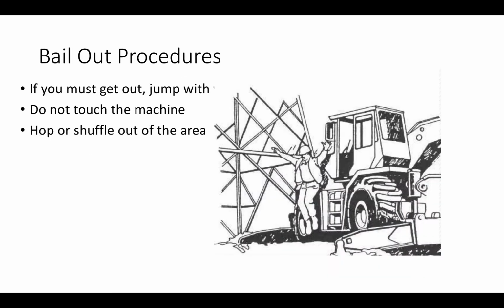If you have to jump out or bail out of a machine that has been connected to a line, jump. Do not touch the machine as you jump. Hop or shuffle out of the area. In other words, you want both legs to be at the same potential. Hopping or shuffling out of the area is the way to do that.